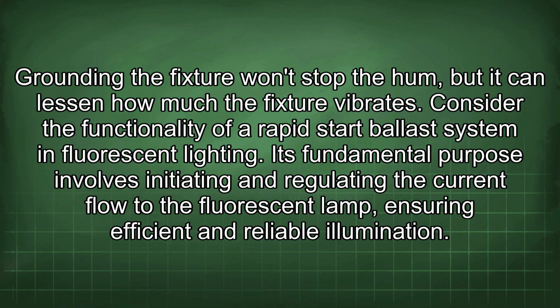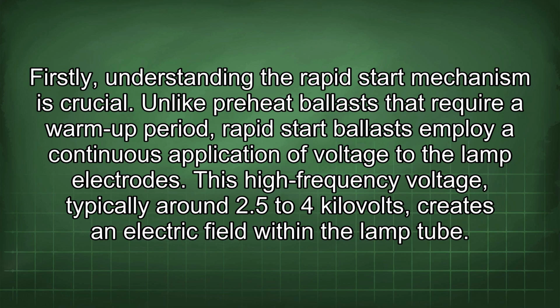Consider the functionality of a rapid start ballast system in fluorescent lighting. Its fundamental purpose involves initiating and regulating the current flow to the fluorescent lamp, ensuring efficient and reliable illumination. Firstly, understanding the rapid start mechanism is crucial. Unlike preheat ballasts that require a warm-up period, rapid start ballasts employ a continuous application of voltage to the lamp electrodes. This high-frequency voltage, typically around 2.5 to 4 kV, creates an electric field within the lamp tube.